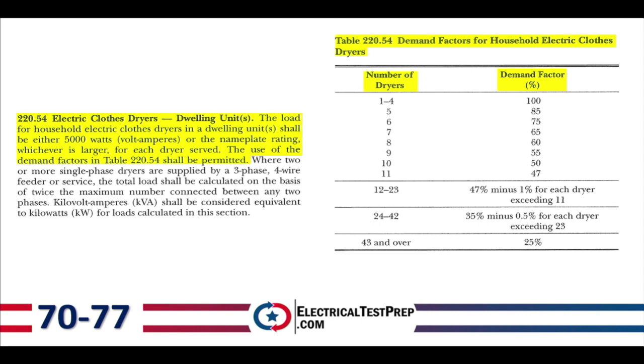Section 220.54, Electric Clothes Dryers. The load for household electric clothes dryers shall be either 5,000 watts or the nameplate rating, whichever is larger, for each dryer served. Table 220.54 demand factors may be used when there are multiple dryers, such as in a multifamily dwelling. Even using Table 220.54, the minimum for an electric clothes dryer in the standard method calculation is 5,000 watts.